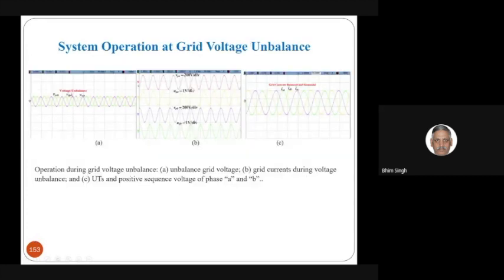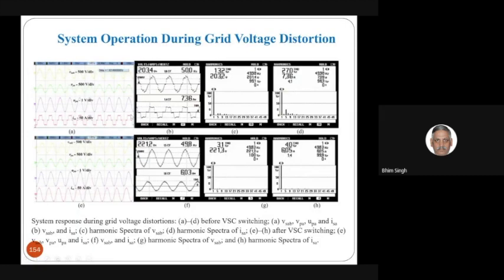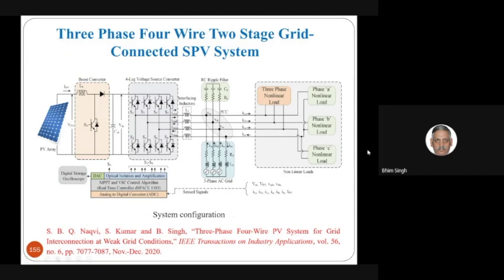And even if the voltages are unbalanced, you are able to get a balanced voltage from the unbalanced voltage and operate the system satisfactorily. And these are typically reasonably distorted voltages. You can see the kind of distortion in the voltage, with around 13.2% THD, with the load current THD 27%, but the grid current THD is only 4%. So it is able to do it, I mean, without much power.